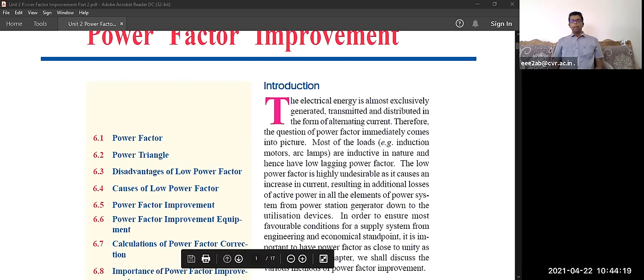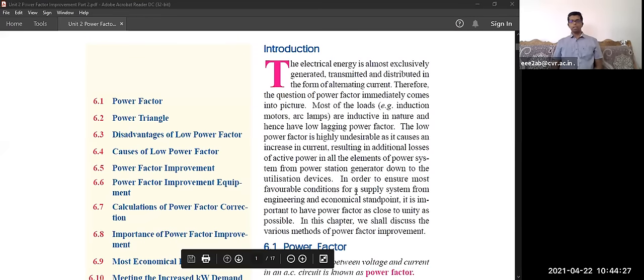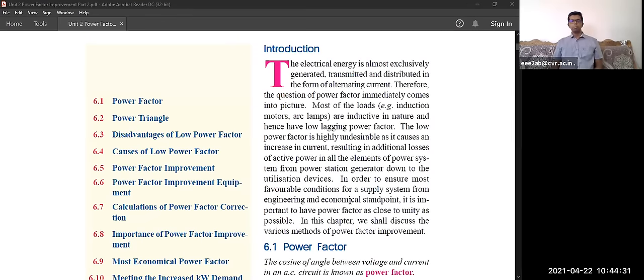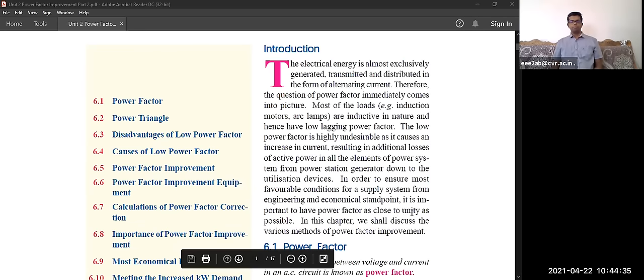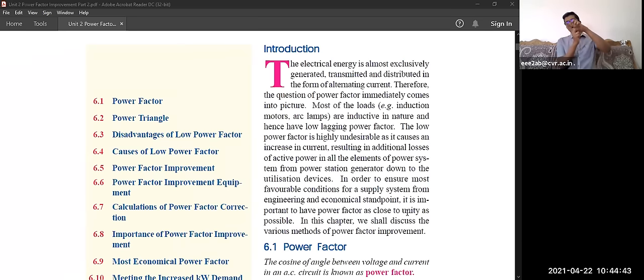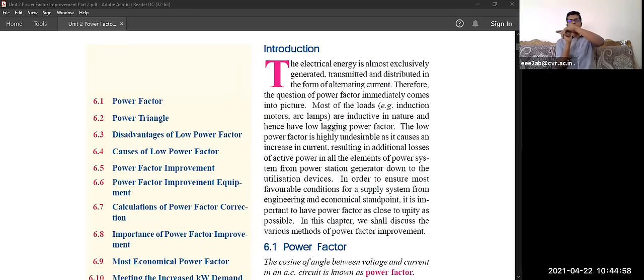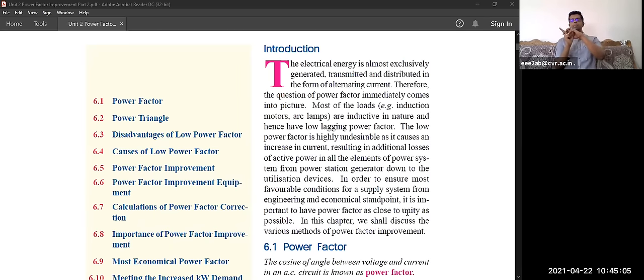We cannot easily replace conductors in transmission lines, so instead we must reduce the power factor problem. Line losses also increase due to higher current, including heat losses in all elements of the power system from the generating station down to the load. From an engineering point of view, it is important to have a power factor as close to unity as possible. Voltage and current should ideally be in the same axis with no phase difference, but inductive loads cause the current to lag.